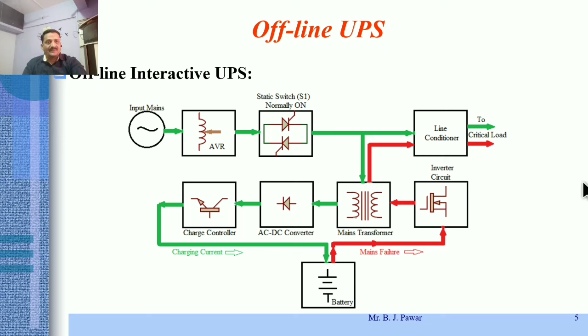At the same time, over here also you will observe the secondary source, that is the DC source battery, which will get charged up through various blocks, the charge controller, then AC to DC converters, etc., then the step down transformer like this. Again, same as the previous type, whenever the power fails or power conditions are not good from the main supply, then the static switch S1 gets turned off and the DC power is delivered to the inverter directly. That inverter converts its input DC to AC, and that converted AC gets delivered to the critical load through the line conditioners. And again whenever power conditions are okay in terms of voltage, frequency, harmonics, etc., then automatically this battery will get charged up. So this is the second type of offline type, that is interactive offline.